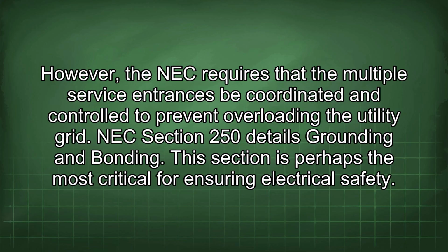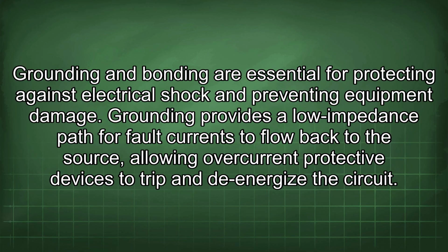NEC Section 250 details grounding and bonding. This section is perhaps the most critical for ensuring electrical safety. Grounding and bonding are essential for protecting against electrical shock and preventing equipment damage. Grounding provides a low impedance path for fault currents to flow back to the source, allowing overcurrent protective devices to trip and de-energize the circuit.